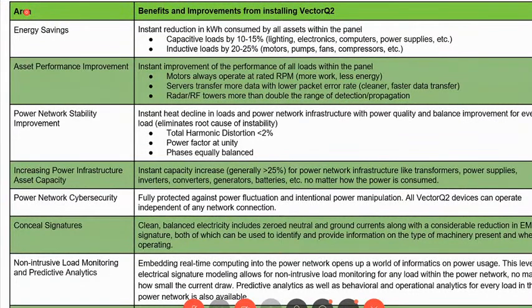Going on, there's the concealment of electrical signatures. Right now, neutral current sniffing or electromagnetic EMI detection is very easy to do from far away. What this device does is it zeroes the ground current, it zeroes the neutral current. It reduces the EMF, it reduces the eddy currents in the upstream transformers, it reduces the signatures related to uncontrolled power, which is also very valuable from a military perspective, I guess.